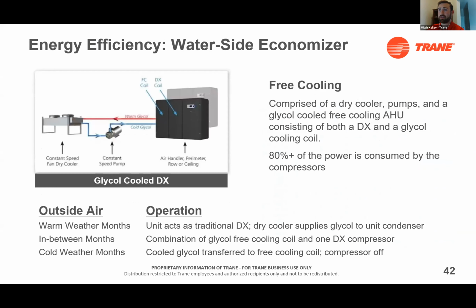In terms of the energy efficiency opportunities doing this, one of the things, if you have what's called a condenser water loop serving self-contained units in your building, so that means that you have a cooling water loop throughout your facility, and then you have individual units with compressors in them to basically reject heat from the room to that water loop, which then sends it outside. You have an opportunity that during the winter time, you can actually use that heat rejection device outside to produce very cold water based on the ambient condition, and use that water to cool your facility as opposed to using mechanical compression. So that's an opportunity for energy efficiency with this system, but also adds a degree of complexity to it that you wouldn't otherwise have.